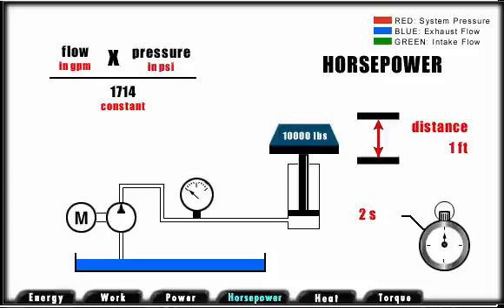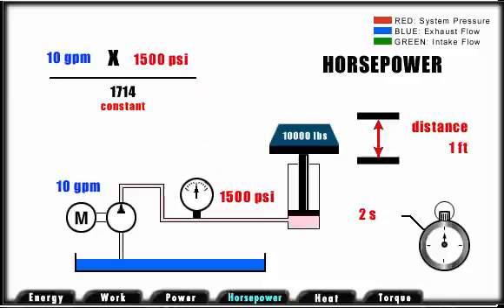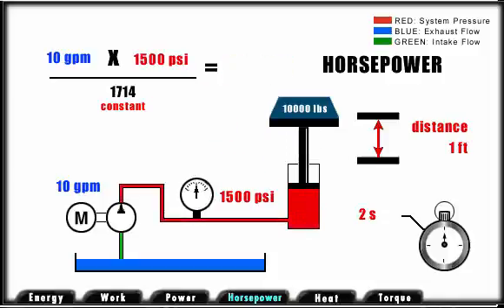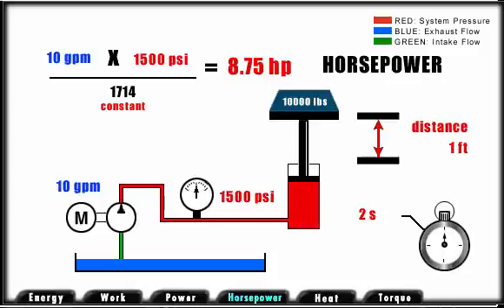In this illustration, a 10 gallon per minute pump is required to extend the cylinder in 2 seconds. The pressure requirement to lift the 10,000 pounds is 1,500 psi, based on cylinder diameter. Based on our formula, our theoretical horsepower requirement would be 8.75.